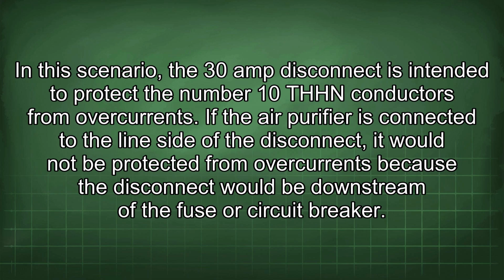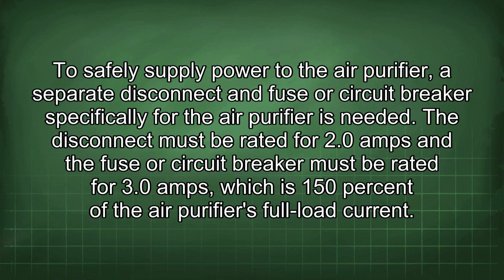If the air purifier is connected to the line side of the disconnect, it would not be protected from overcurrents because the disconnect would be downstream of the fuse or circuit breaker. To safely supply power to the air purifier, a separate disconnect and fuse or circuit breaker specifically for the air purifier is needed. The disconnect must be rated for 2.0 amps and the fuse or circuit breaker must be rated for 3.0 amps, which is 150% of the air purifier's full load current.